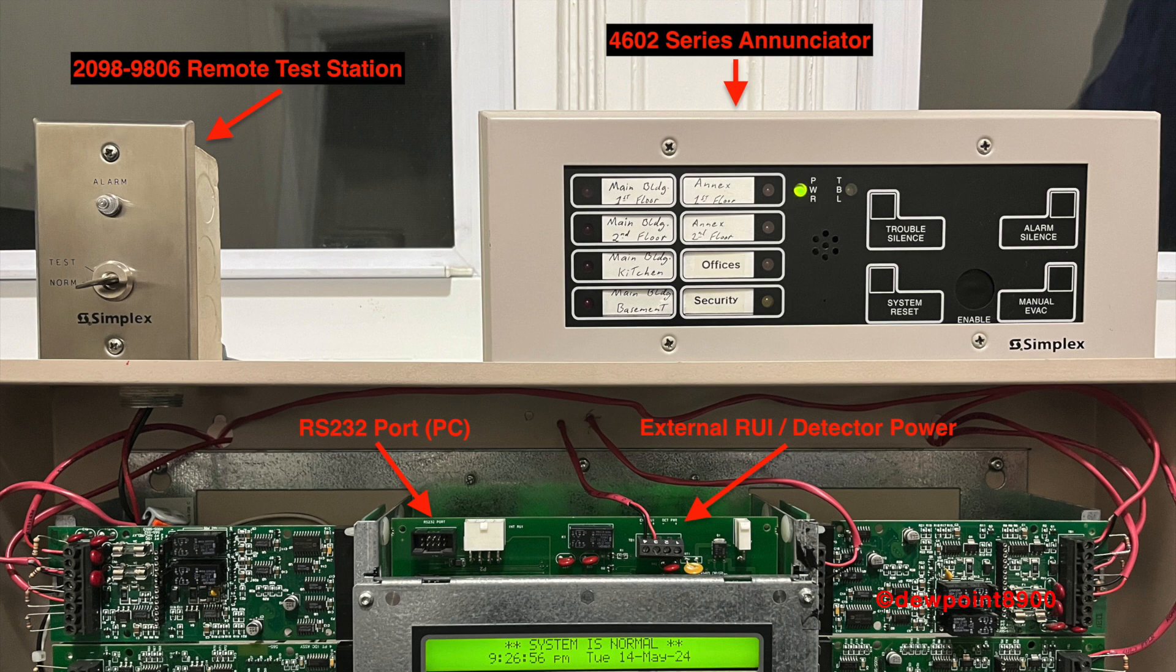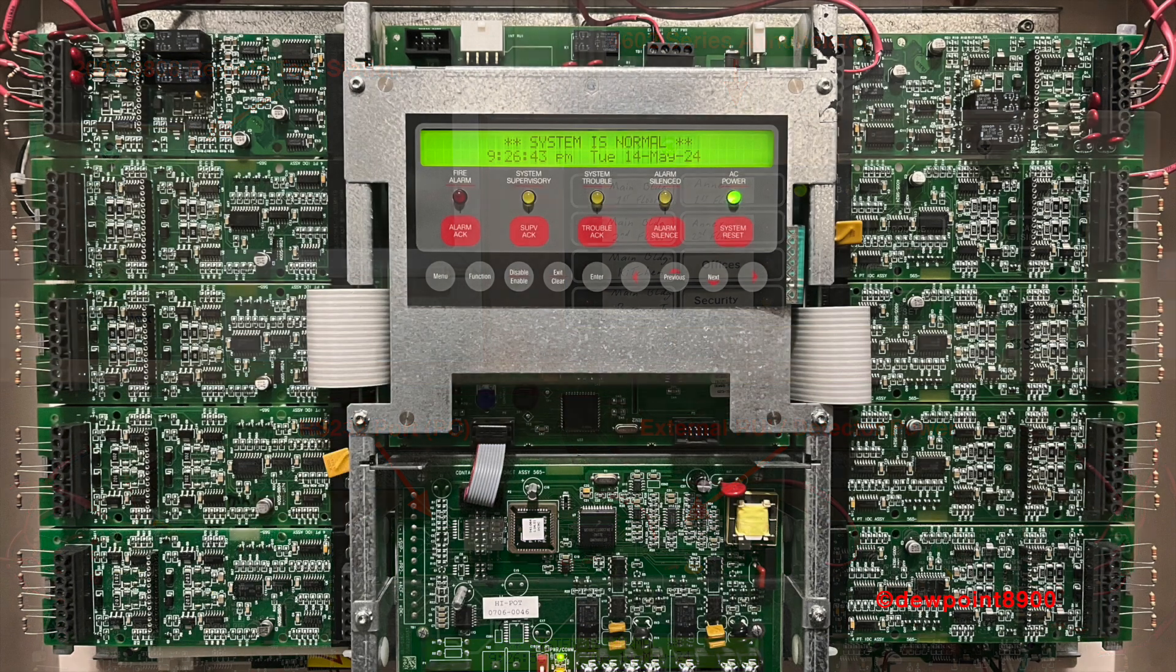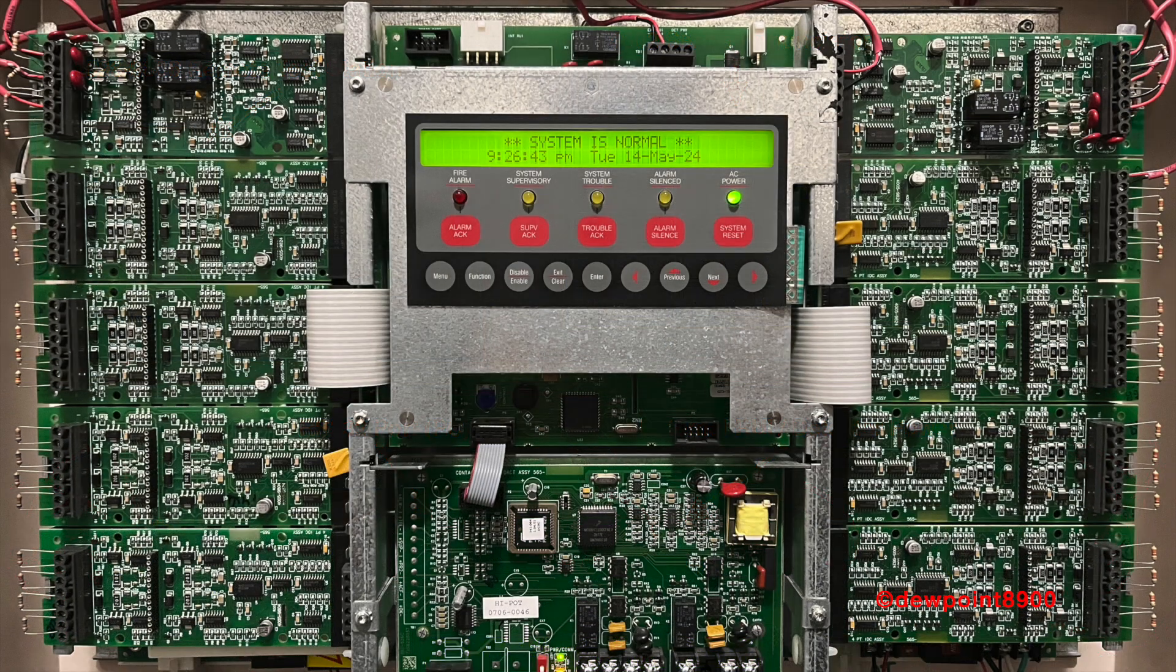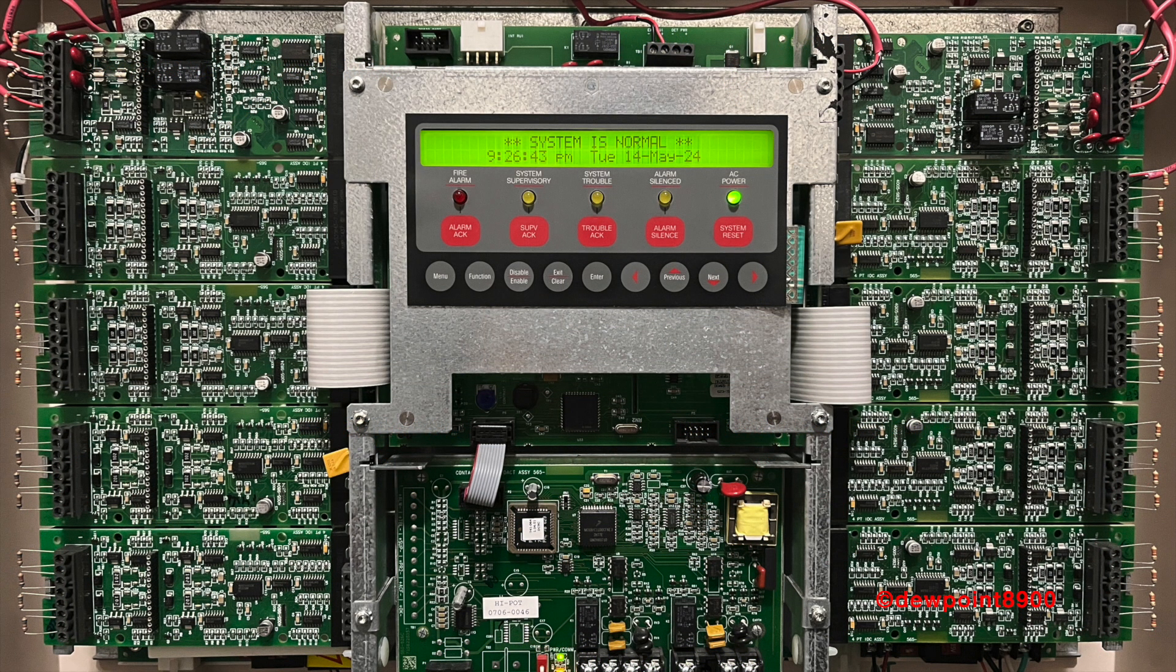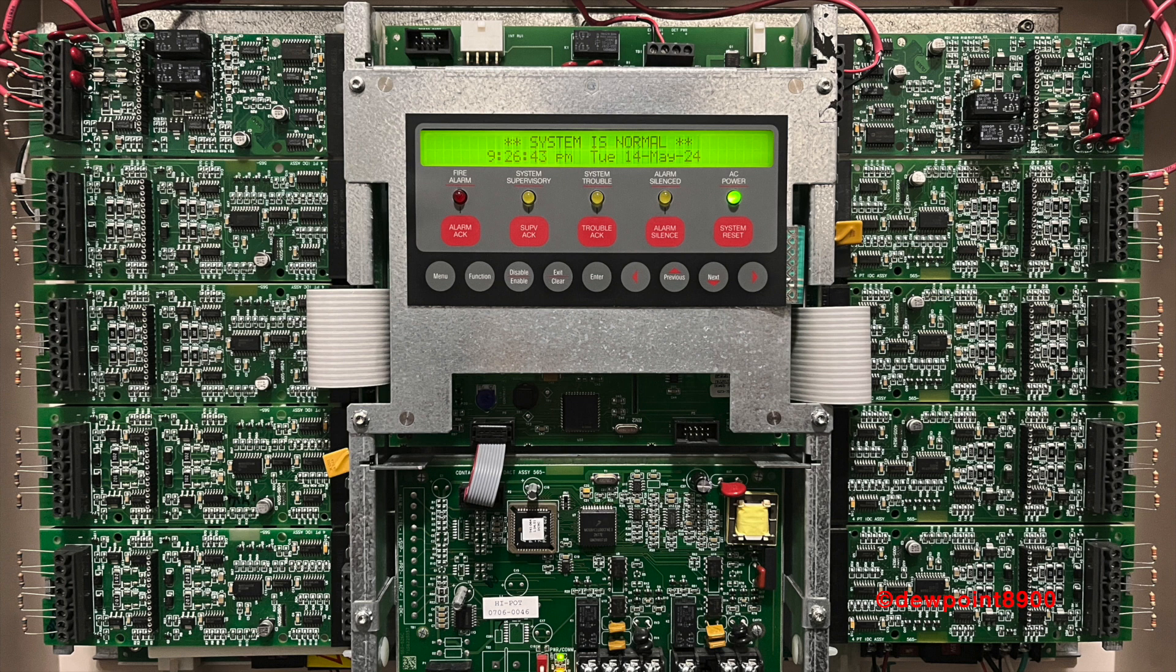Below the CPU card, there is a slot for a DACT communicator or two city circuit modules. The main power supply is mounted on the bottom-right side behind the modules. It connects to a power distribution board, where the modules will be inserted. In addition to providing power for the modules and the CPU, there are two auxiliary power taps on the board, providing constant 24V for external peripherals like annunciators.